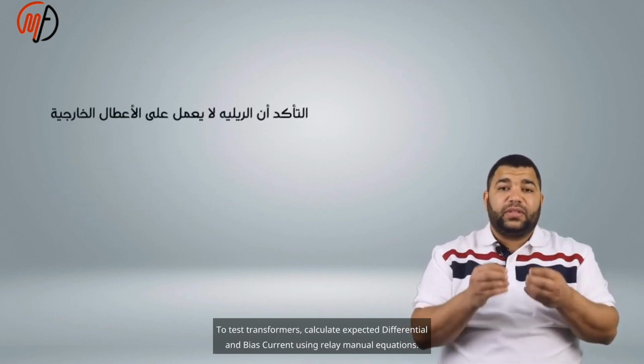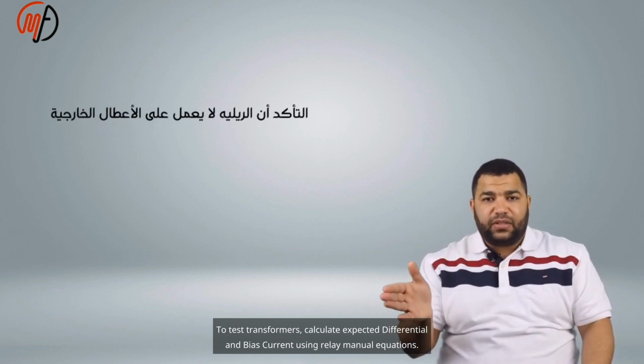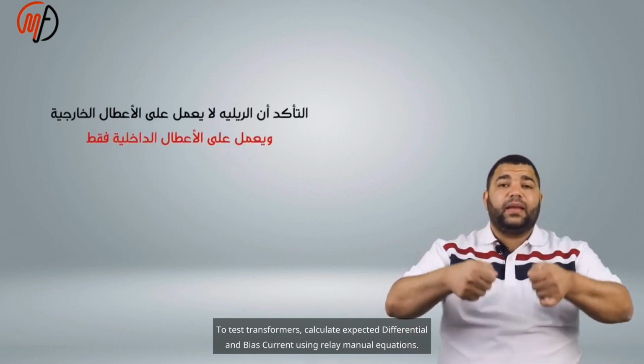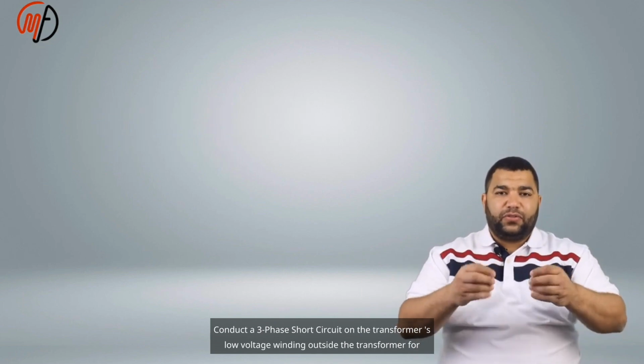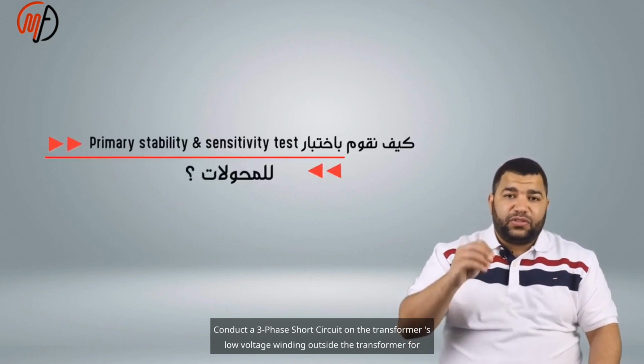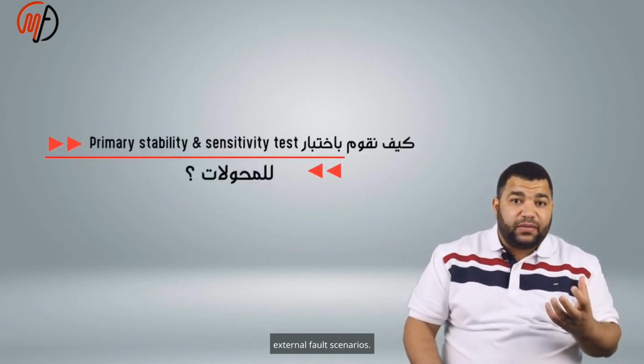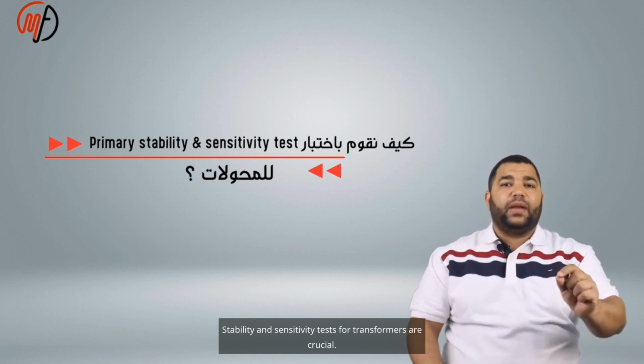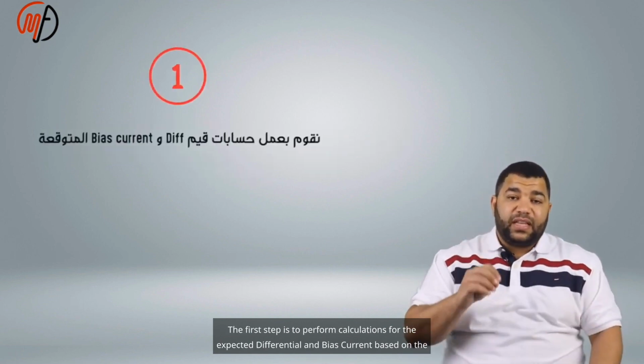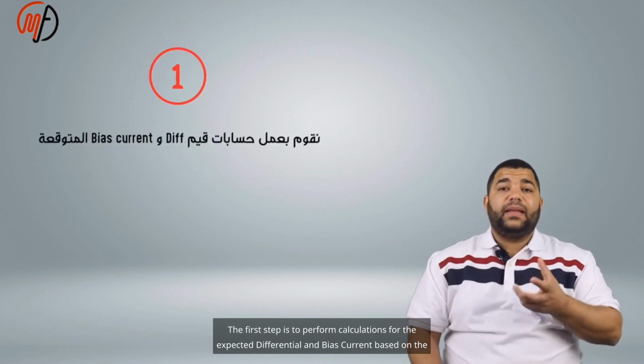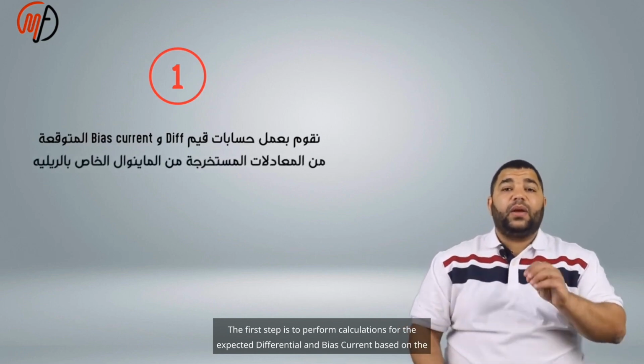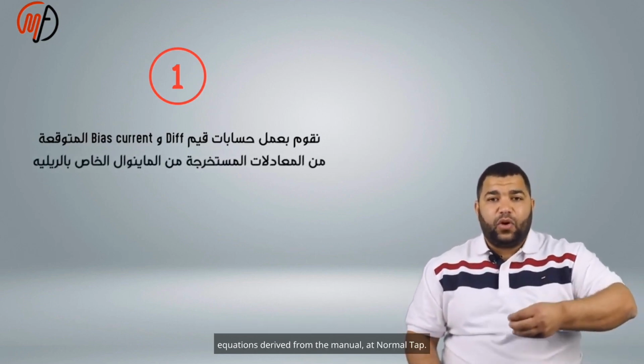To test transformers, calculate expected differential and bias current using relay manual equations. Conduct a three-phase short circuit on the transformer's low voltage winding outside the transformer for external fault scenarios. Stability and sensitivity tests for transformers are crucial. The first step is to perform calculations for the expected differential and bias current based on the equations derived from the manual at normal tap.